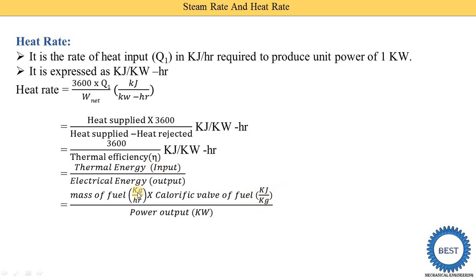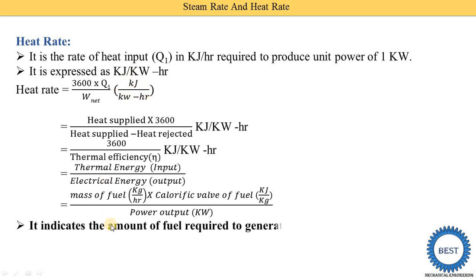In the thermal efficiency equation, the unit in the numerator is mass of fuel in kilogram per hour multiplied by calorific value in kilojoule per kg — the kg cancels, leaving kilojoule per hour. This divided by kilowatt gives units of kilojoule divided by kilowatt-hours. This indicates the amount of fuel required to generate one unit of electricity — by using heat rate, we can find the amount of fuel required to generate one kilowatt of power.